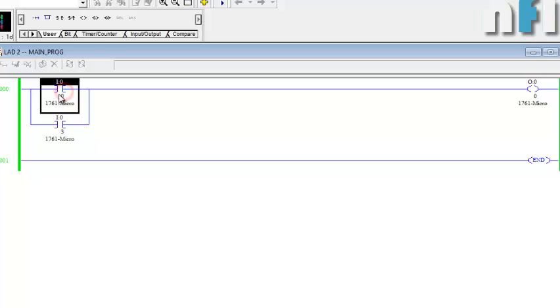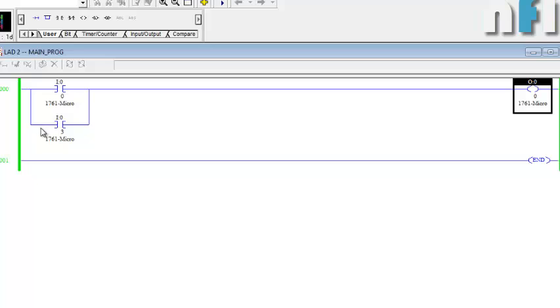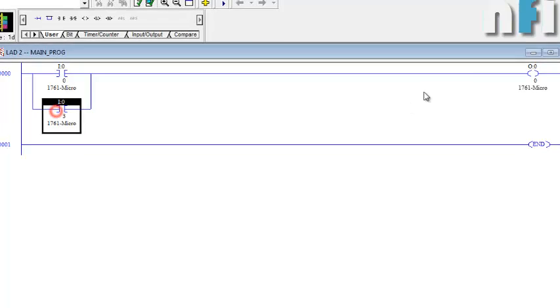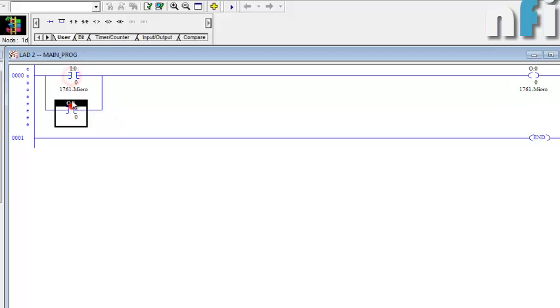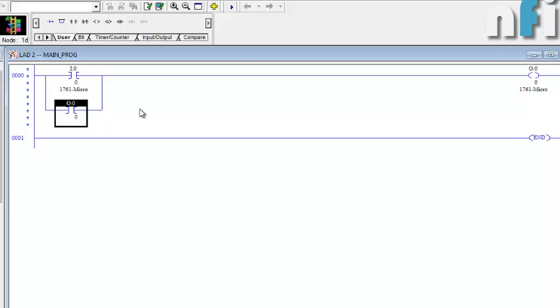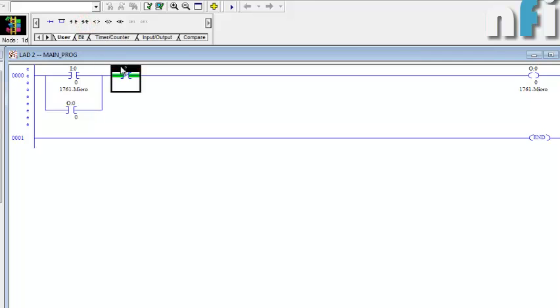Now suppose you want the output to be latched — meaning if you press the button once it should remain on. It's simple: transfer the output address here as an auxiliary contact. When you press the button, the output is energized and the auxiliary NO bit at the same address keeps it on. To unlatch it, add an NC contact with address I:0/3.